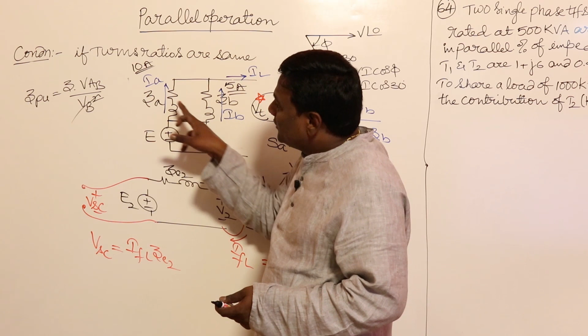Okay. So for example, whenever this is 10 amperes, let me think of this particular ZA value as 0.1 ohm, just like a resistance. So 10 amperes into 0.1 is going to be 1 volt. Whenever 1 volt is happening here, how much current should flow? 5 amperes should go. Means that the impedance of this should be 0.2 ohm. Whenever you have the same voltage across this, 5 amperes should go. Means that if this impedance is 0.1, this impedance should be 0.2 ohm. So 10 amperes into 0.1 should be equal to 5 amperes into 0.2, or 10 kVA into 0.1 should be equal to 5 kVA into 0.2.